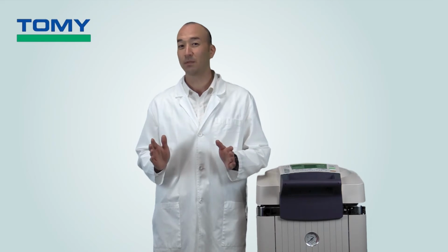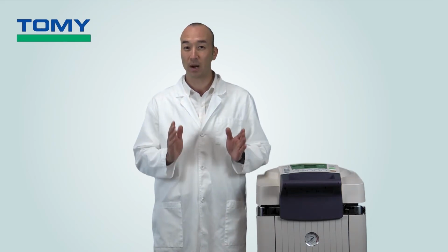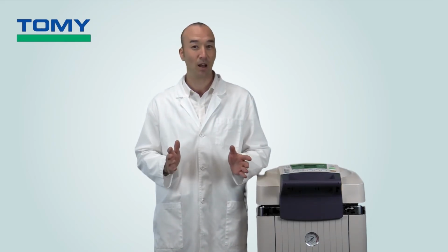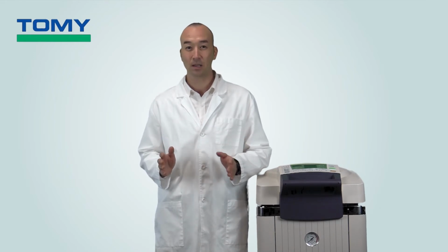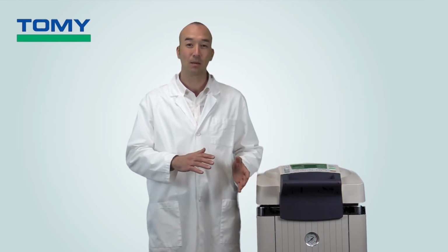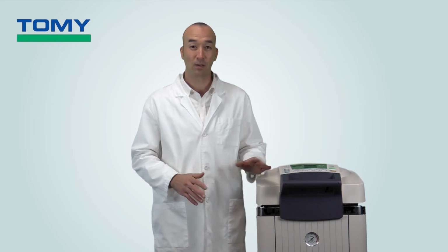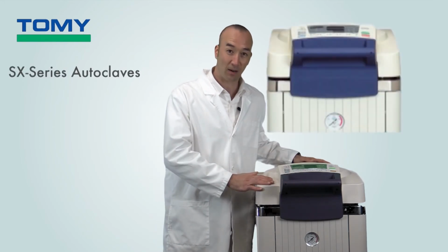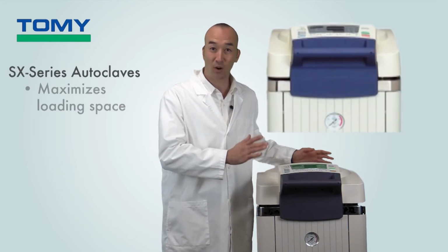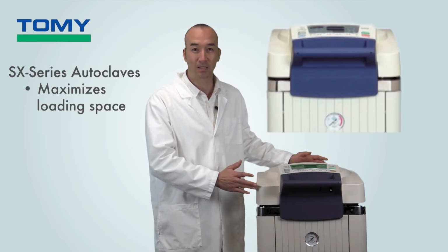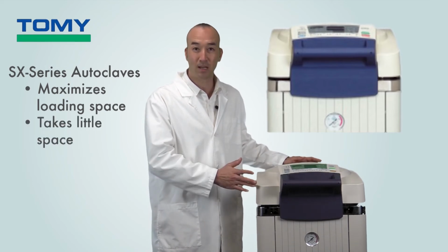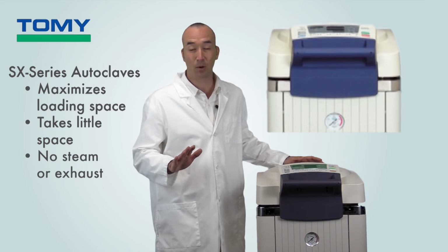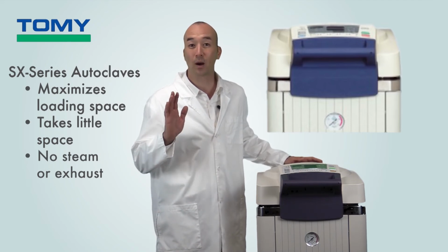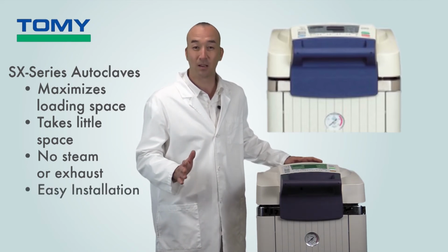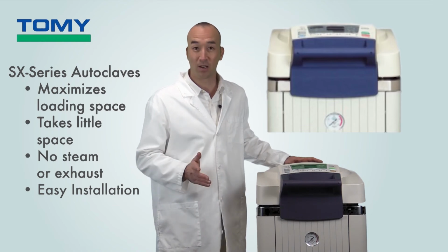Due to the simplicity of the gravity autoclave, which requires a heater, intake, and exhaust valves, there's a great range of designs, including front and top loading types. Top loading autoclaves, like this Tomy SX series autoclave here, are advantageous because their vertical design maximizes loading capacity, takes up little floor space, and doesn't require any steam or exhaust connections. All it requires is a small space to put it, a source of electricity, and you're good to go.